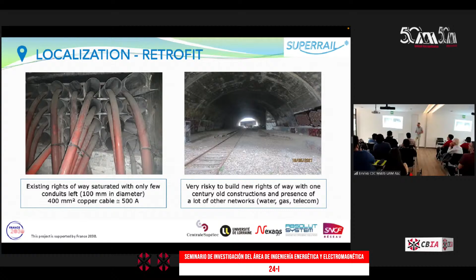So these are the specifications of the cable. In fact, it is not one cable; it is 2 cables. The rated voltage on the network is 1,500 volts DC, and the rated current is 1,500 amps. But in fact, due to the acceleration of the train, at some times during a few seconds, maybe minutes, the cable must be capable of transmitting 3,500 amps. So this is why the critical current of the cable should be higher than this value. The return of the current is not made in the second cable or in a coaxial way. The return part of the current will go through the rail and through the ground.